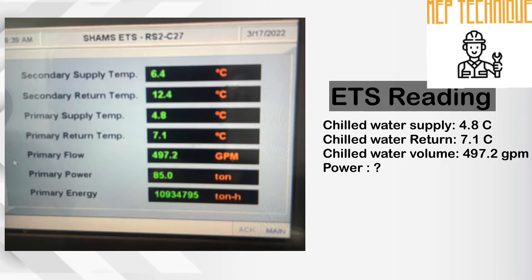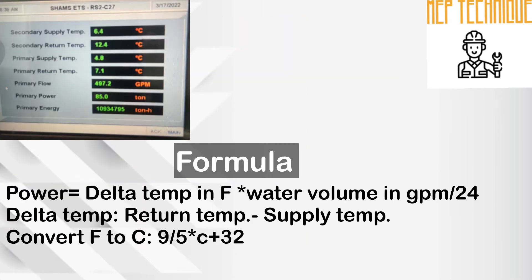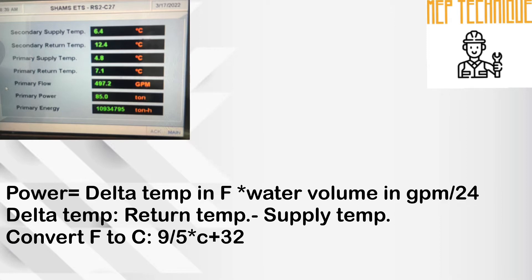We have to calculate the power by putting our formula. The formula of power is delta temperature in Fahrenheit multiplied by water volume in GPM, divided by 24. The formula to calculate delta temperature is return temperature minus supply temperature. To convert Celsius to Fahrenheit, the formula is F = (9/5)C + 32.